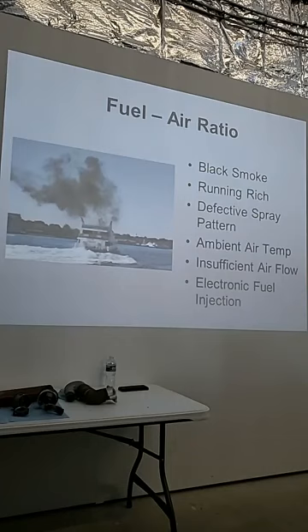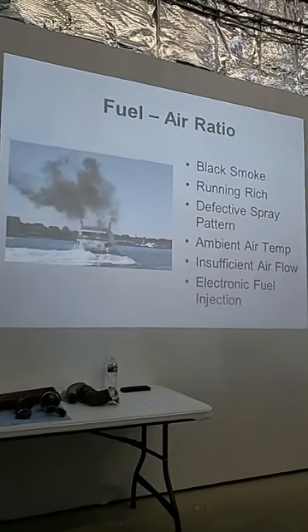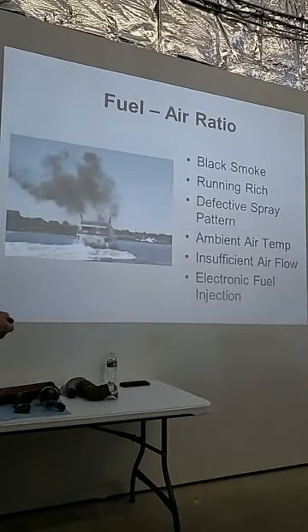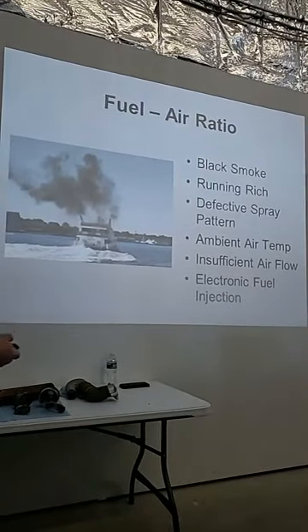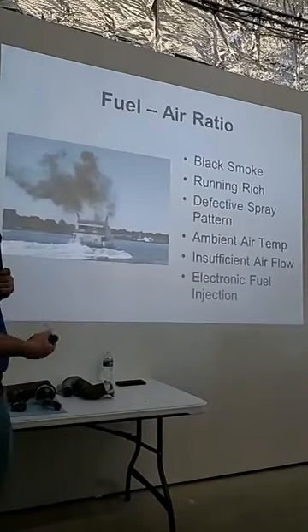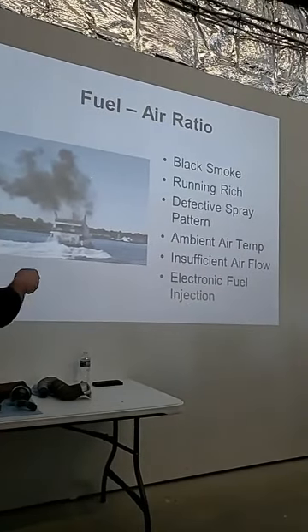Black smoke is from running rich. It can be caused by defective spray patterns, ambient room temperatures, or insufficient airflow either into or out of the engine. Electronic fuel injection does away with this.